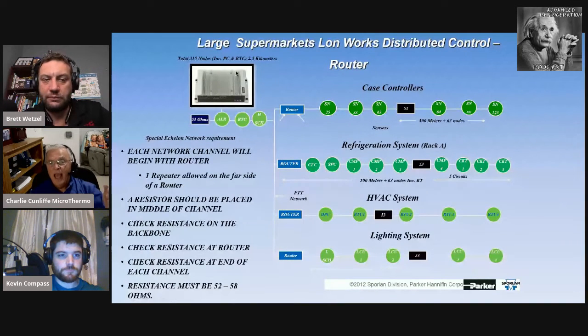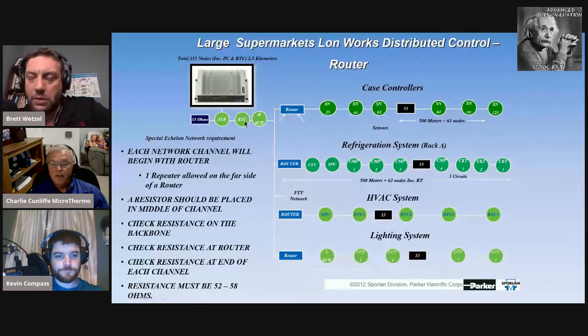Should something happen to this HMI, everything will synchronize to the alarm node, which has a real-time clock. If anything happens to the alarm node, each of these nodes has its own internal countdown clock, but it will be self-operating at that time, meaning if it's a case controller, it will continue running the lights, fans, and superheat, but it won't be synchronized to the alarm node. So everything synchronizes to the HMI, that's how you report out to the real world. Should anything happen here, everything synchronizes to the alarm node with its real-time clock, and if anything happens there, they work off their own internal clocks.